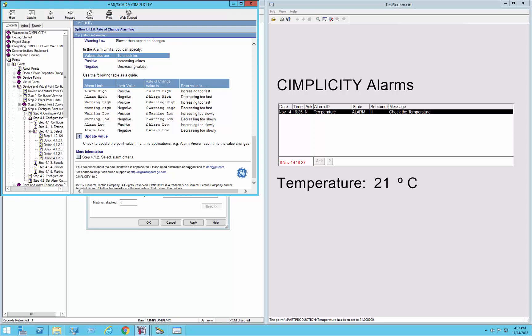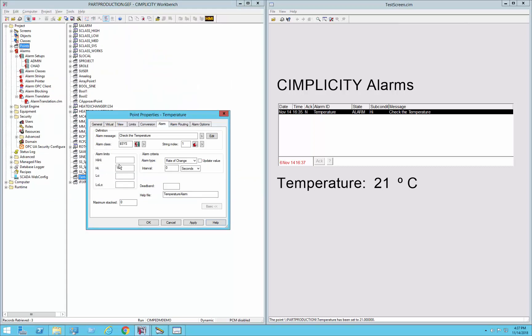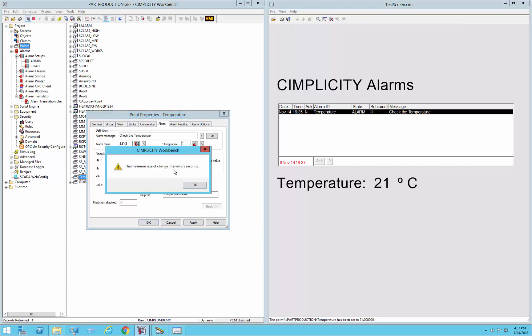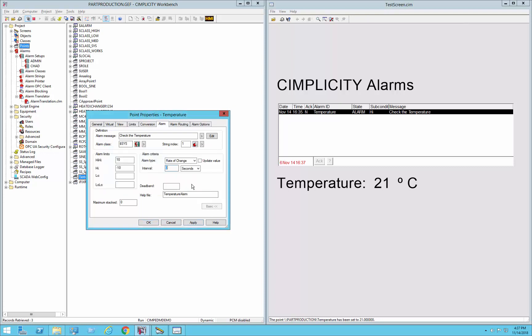So in our case, what we'll do is we'll say that if a value goes up by 10, more than 10, then that's a rate of change alarm, or down faster, more than 10, that will be a rate of change alarm for us. Now the minimum change or interval rate that you can specify is 5, we're going to say 10 for our case, and we'll apply that.